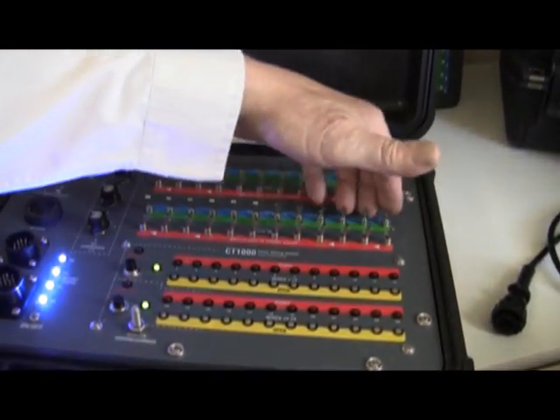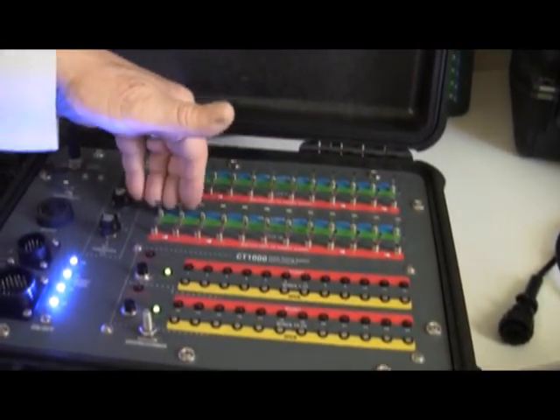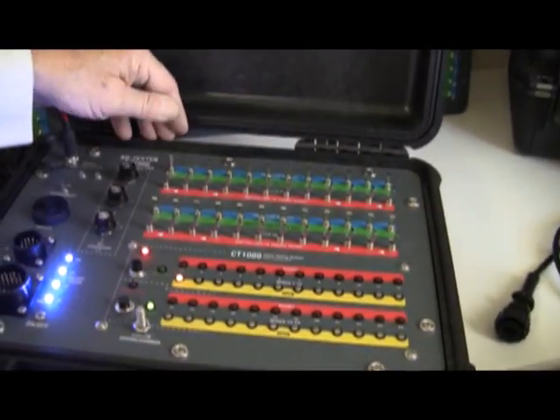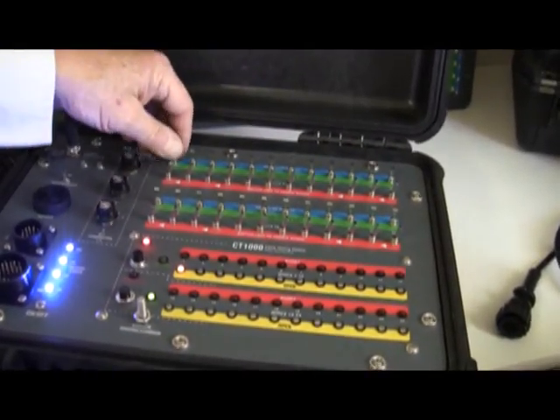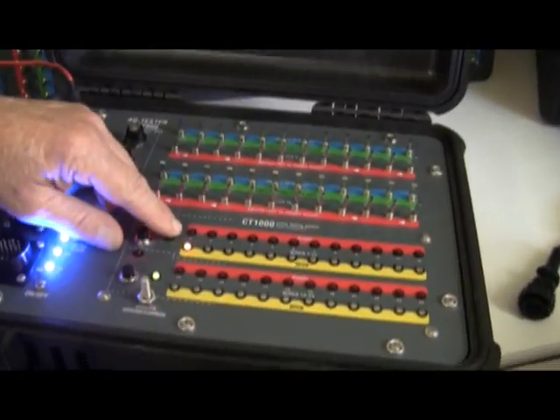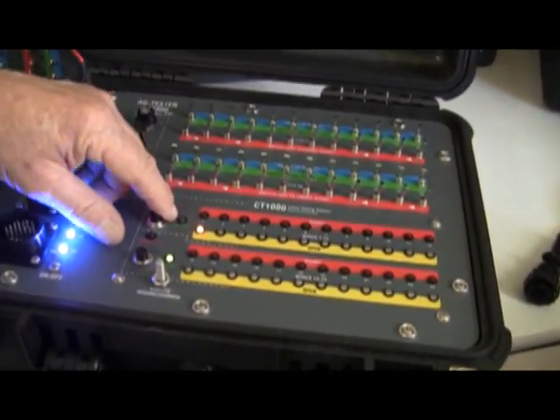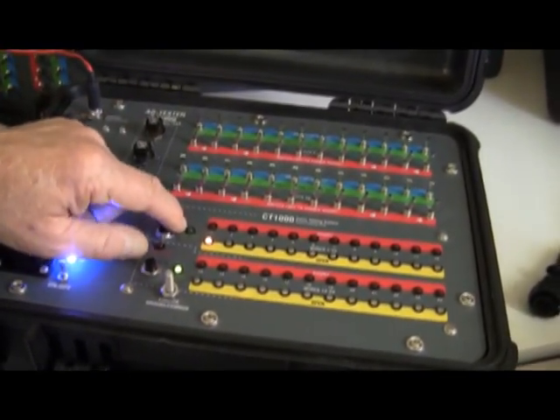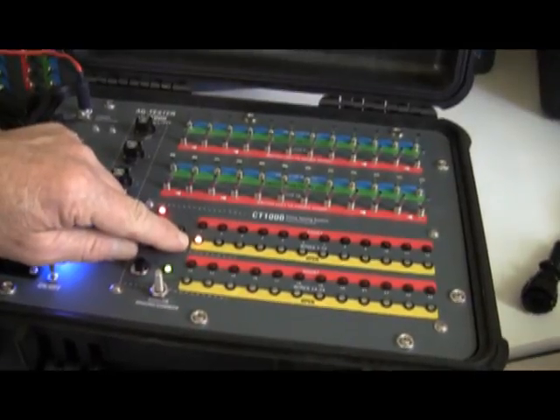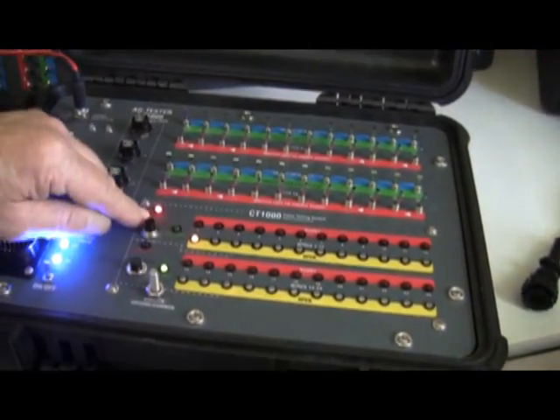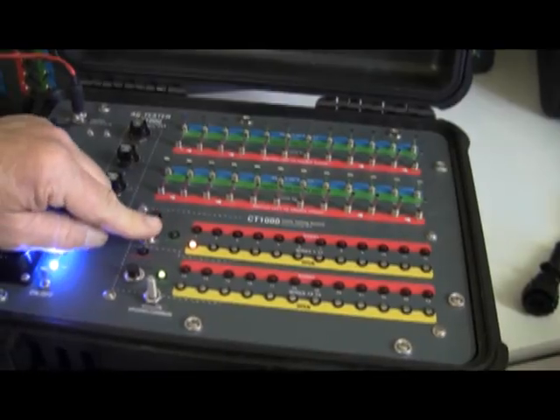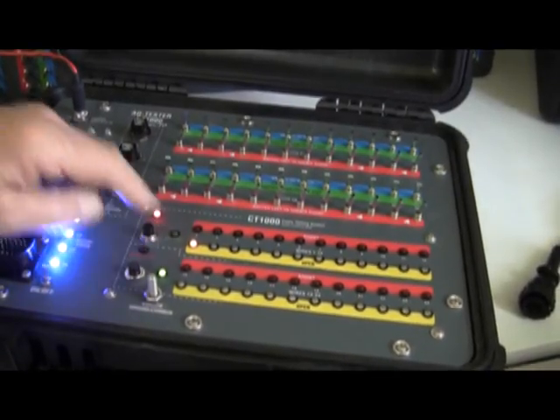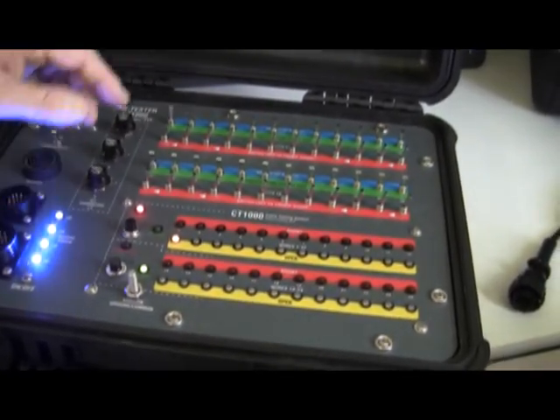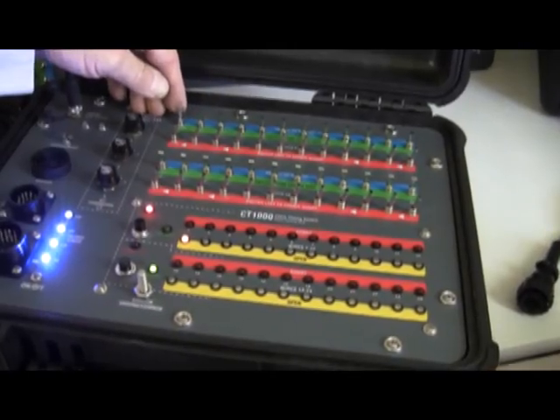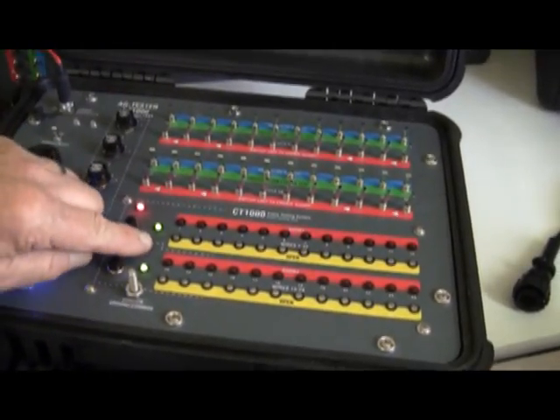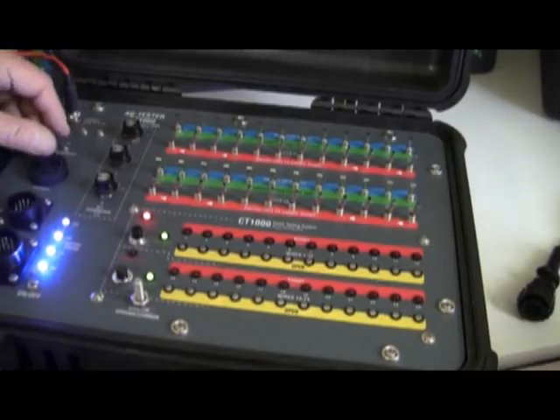I'm going to go ahead and run a test. So I turn on wire 1, and a couple of things happen: the green all-okay light disappears, it now shows an open condition, and we get an alarm. I can't reset the alarm until the problem goes away. If I turn wire 1 back off, the OK ready light comes back on.